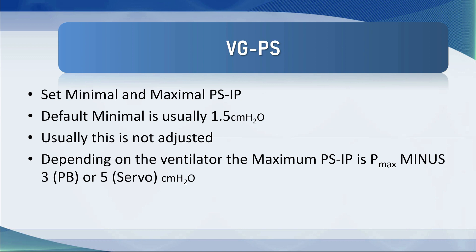You would normally set a minimal and maximum inspiratory pressure in volume guaranteed pressure support, but the default in most ventilators is fine — it's usually about 1.5 centimeters of water, which is just the base flow going through the system. You don't want someone getting 700 to 800 mils when they have normally compliant lungs; you want them to get the minimum support they need. The maximum pressure support level is the Pmax minus three on the Puritan Bennett or minus five on the Servo.